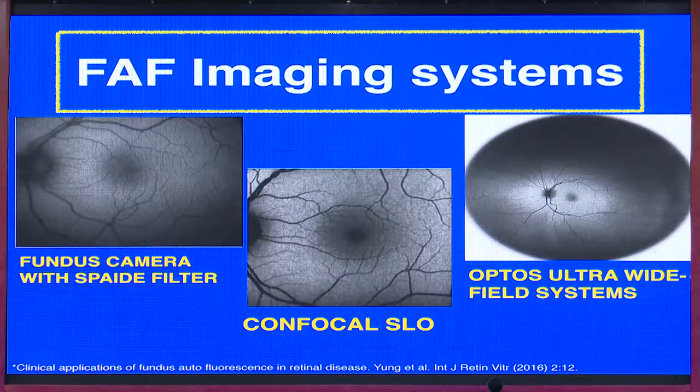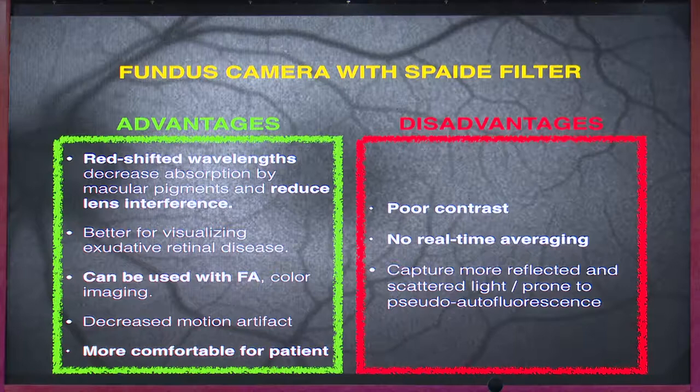Let's look at the imaging systems available for autofluorescence. We have the basic fundus camera with a Spaide filter — that is a red-altered filter — we have a confocal scanning laser ophthalmoscope, and we have the Optos ultra-widefield system. The advantage of the fundus camera with the Spaide filter is that it has been converted to a red-shifted filter so it doesn't interfere with other ocular structures that emit autofluorescence.